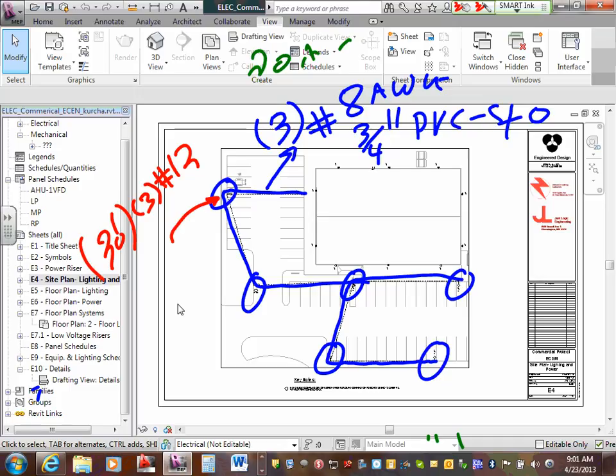Don't forget, guys, that your mechanical equipment is going to be coming from here. We're not showing our electrical equipment. Your electrical equipment is going to be coming this way too, so you have to trench for your electrical equipment. You have to accommodate for feeders for electrical equipment, as well as, what did we say yesterday? We said meter center. Your meter center is going to be somewhere here. Termination box, my termination box. Any comments, guys? Any questions? Is this enough information to get you guys up and running? Is that cool? Is that good enough to get you up and running?